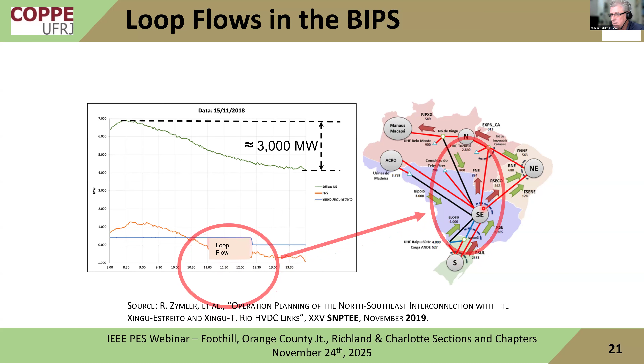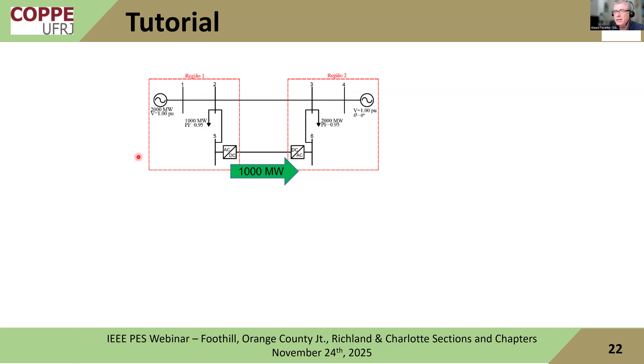Okay, so you have this loop flow. It's very easy to understand with a tutorial system here. When you have AC in parallel with the DC, let's say you have 2 gigawatts of generation here, 1 gigawatt of load here, 2 gigawatts of load here, and you set 1,000 megawatts in the DC line. Basically you don't have transmission in this AC line, because you have 1,000 megawatts going here, 2,000 being generated here, 1,000 goes to the load, and 1,000 comes here. But if you don't control the generation, and generation goes down in this area and goes up in this area, you can create a loop flow, because if you don't change this set point, you create AC flowing from right to left.